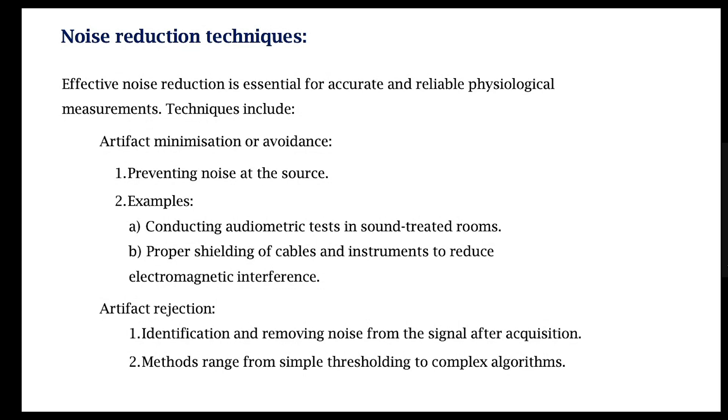For example, if you are interested in conducting an audiometry test, it is best to conduct this test in a room that is soundproofed. You can also provide shielding to the cables and instruments to minimize electromagnetic interference. That will reduce the amount but will not actually remove it, so you are minimizing the interference or noise at the source.